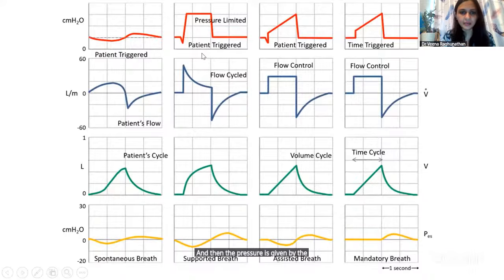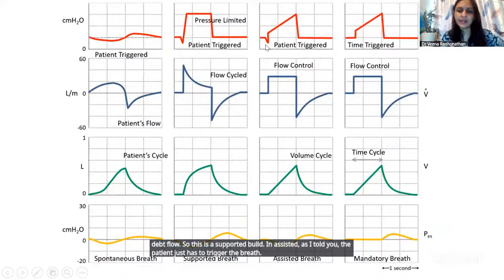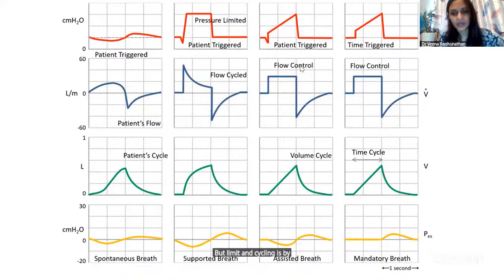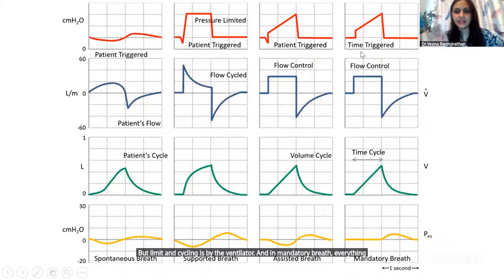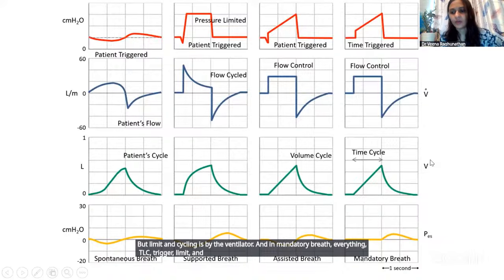So in a supported breath, the patient triggers and then the pressure is given by the ventilator as per the limit set, and the flow cycling happens as per the patient's breath flow. So this is a supported breath. In assisted, as I told you, the patient just has to trigger the breath, but limit and cycling are by the ventilator. And in a mandatory breath, everything, trigger, limit, and cycle, is all by the ventilator.